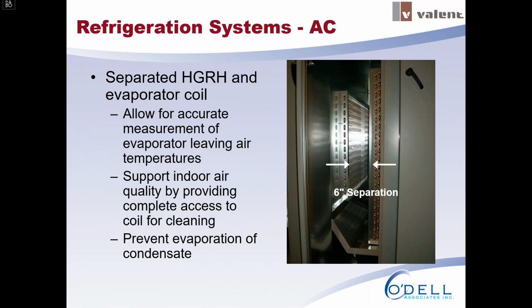So in addition to having hot gas reheat, it's also advantageous to have a modulating valve for that reheat. So the DX coil, like I said, we're cooling down to a certain dew point temperature. And then we want to be able to control how much reheat we have. And we do that with a modulating valve. So again, we're all about tight control. And one of the things that helps us control that very tightly, it may not seem significant, but it really is, is the separation between the DX coil and the hot gas reheat coil. And it's typically about 6 inches in our models. And you'll see that picture shows that 6-inch gap.